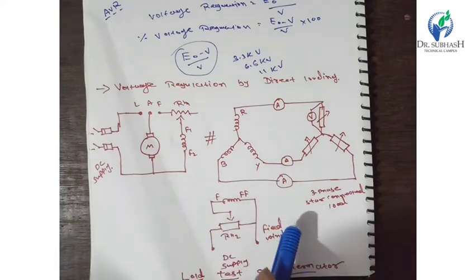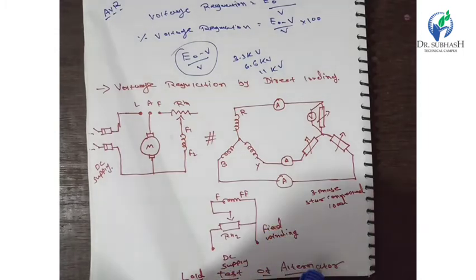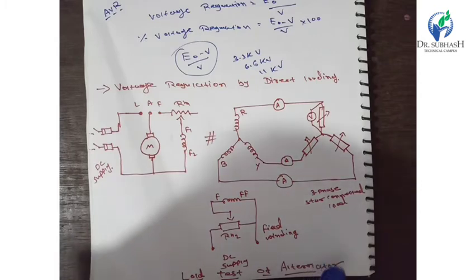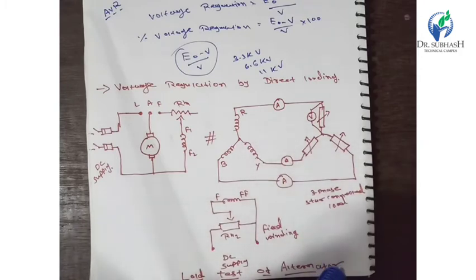The readings at any load condition from no load to full load are taken. Now, 4 to 5 observations can be taken, and the last observation should be at the no load condition, where the load on the alternator is thrown off while maintaining the speed and excitation constant. The regulation of the alternator can be calculated from the observation table.